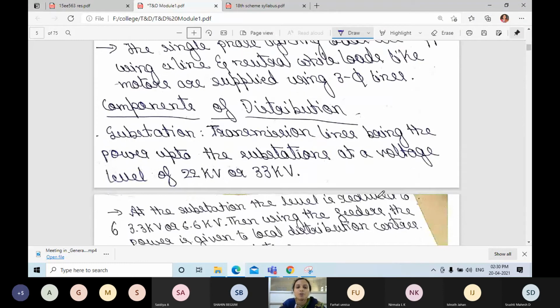Next, we shall discuss the components of distribution. That is, first is a substation. Substation, here transmission. You already know about substation. We have discussed that. Receiving station. Okay, and primary transmission, secondary transmission. Okay, that is what it is here. Transmission lines bring the power up to the substations, that is at a voltage level of 22 kV or 33 kV. At the substation level, it is reduced to 3.3 kV or 6.6 kV. Here 22 kV or 33 kV will come to the substation. Okay, that is reduced to 3.3 kV or 6.6 kV in the substation.